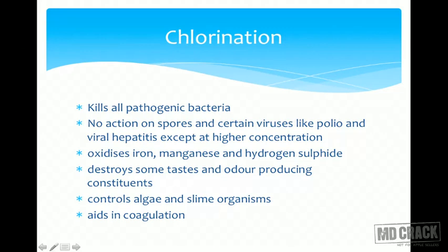Chlorine also oxidizes iron, manganese, and hydrogen sulfide. It destroys some taste- and odor-producing constituents, controls algae and slime organisms, and aids in coagulation. So chlorine has a long list of functions beyond just killing bacteria. One of the most important benefits is residual chlorine — protection against subsequent contamination — which is a fairly unique property. Very few agents have residual protection, and this is why we use chlorine most frequently.